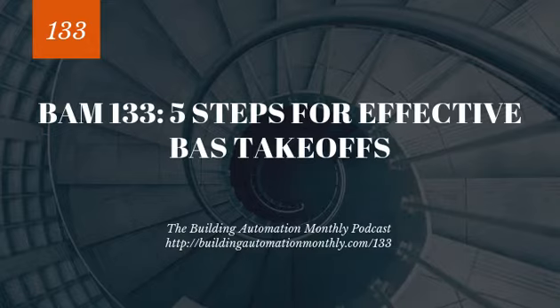That can be a competitive advantage for a salesperson who reads the specification, understands that 4 to 20 milliamp sensors for duct probes is probably not necessary. I would argue it's not necessary at all. That being said, you go and you submit a request for clarification or a request for information, and you're able to adjust your scope of work. Now, I know on some projects, all RFIs and RFCs become public knowledge, and so you're actually helping your competitors, but that's assuming your competitors go and read the RFIs and RFCs and aren't sitting in there playing toss a number and just hoping that they're low.